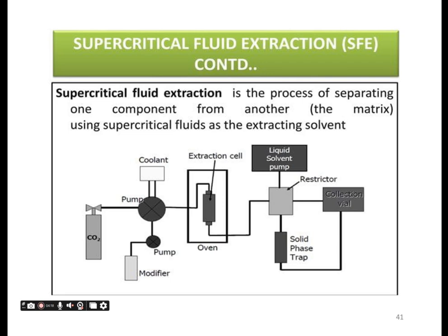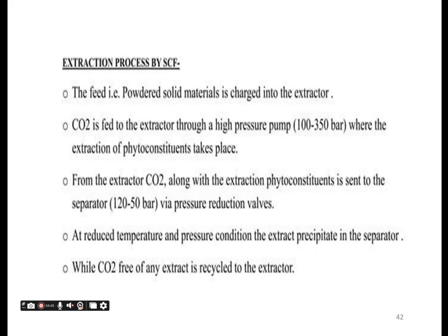So next is the instrumentation. Here is the assembly. This is the cylinder. This here is the pump. Here is the extracting cell, and here is the recycling phase, where we collect the supercritical fluid by the trapping method, and here is the recycling pump. Due to this, it is again compressed and converted into the gaseous state.